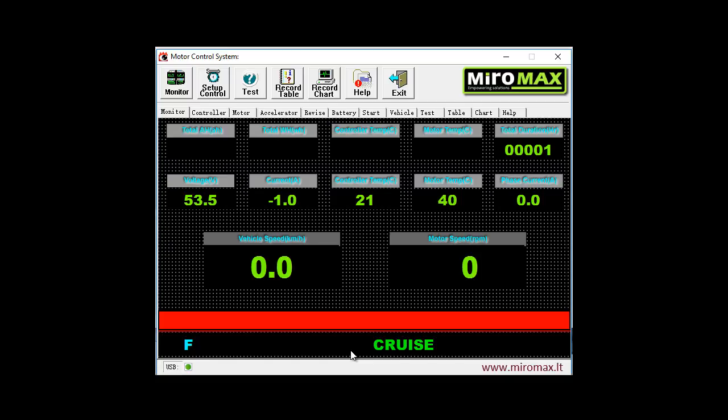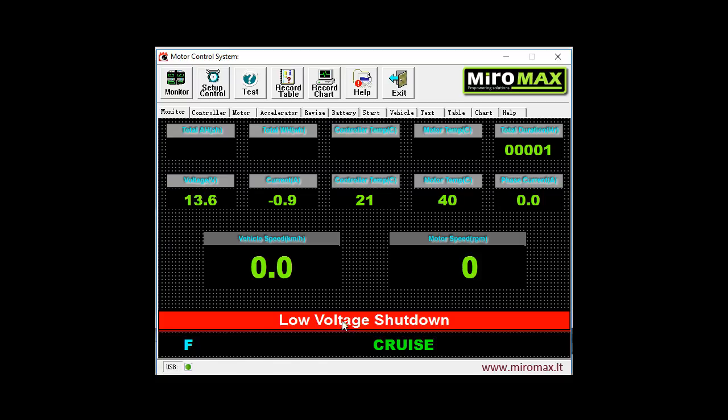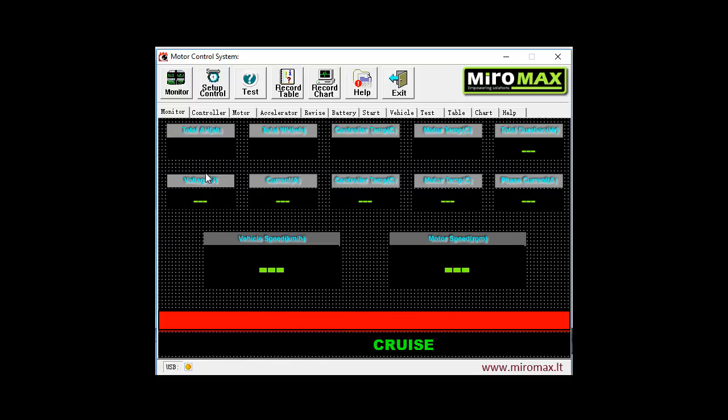Slightly higher in the red line we can see error messages which are displayed if some error appears. For example, if we switch off supply voltage. After some time when the actual supply voltage falls, you can see that a respective message appears about the error, which in this case is low voltage shutdown. In other cases, if other errors happen, respective messages are displayed in this red line.